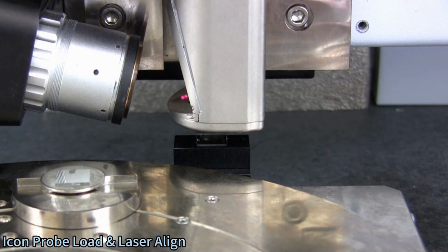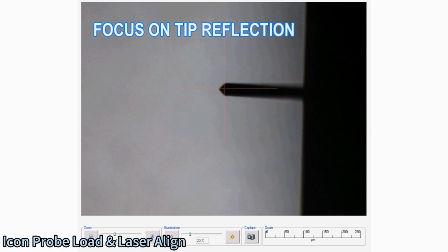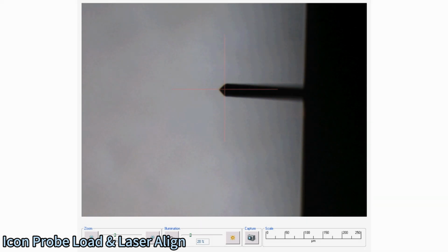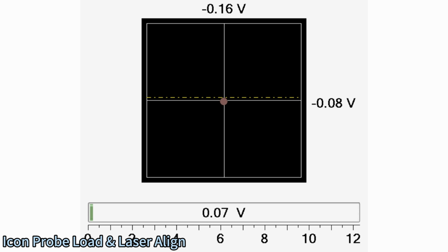Lower the focus to see the tip reflection image, and then move the alignment knobs until you see the laser spot visible near the end of the cantilever. As the laser moves over the cantilever arm, the sum signal should start to increase.